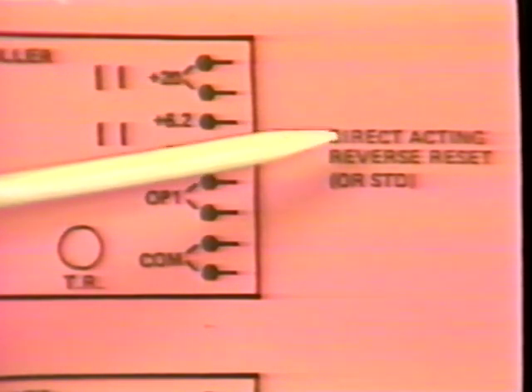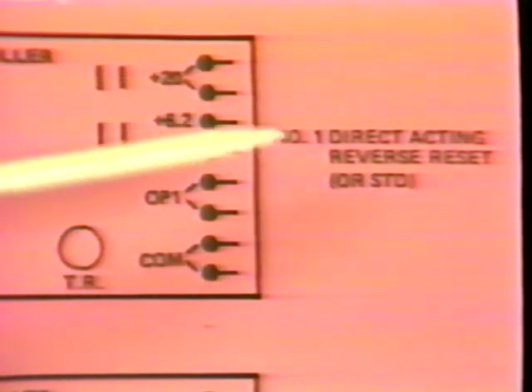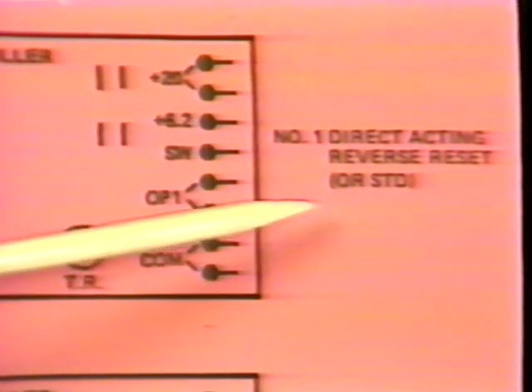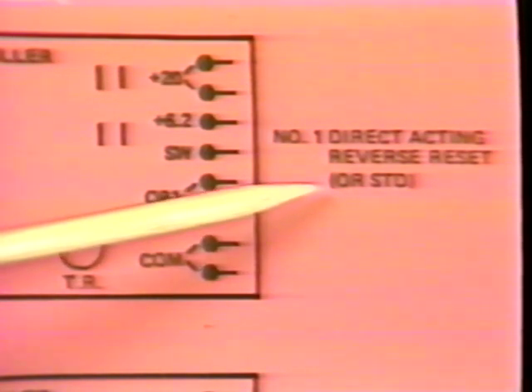This diagram illustrates reverse action. The controller signal is still increasing, but now it increases with a decreasing variable. So variable decrease, controller signal increase, reverse action. There are 4 possible combinations of action and reset with the CP8102. The parallel lines here and here represent the 2 sets of action jumpers. Remember, parallel indicates direct. Since the upper pair is parallel, the controller itself is direct acting. Because both sets match, the reset is reverse. This example is the standard factory position for these jumpers.